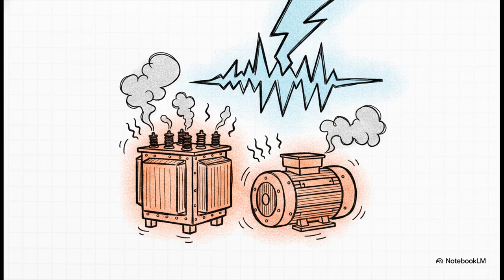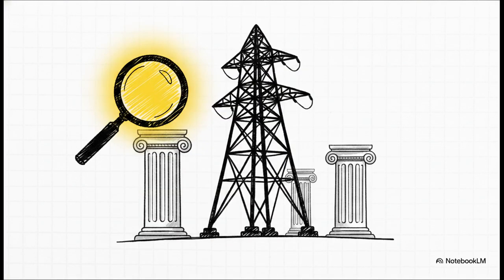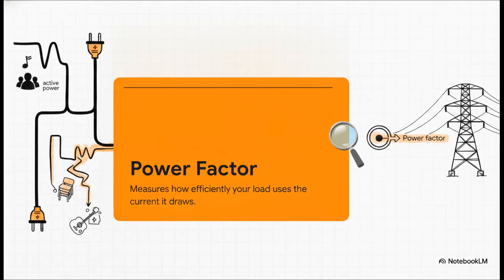So to protect the grid from that unseen damage, regulators have to look way beyond simple voltage boundaries. To stop all that electrical pollution, 3 more parameters get tightly regulated: power factor, total harmonic distortion, and phase imbalance. Each one basically caps a very specific type of grid damage. If you want to connect to the grid, you've got to manage all 3 of these pillars of clean power. Now for today's explainer, we're going to focus entirely on the first, and honestly perhaps most heavily monitored parameter of the bunch: power factor. Power factor simply measures how efficiently your load uses the current it draws.